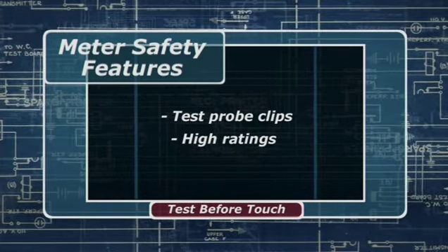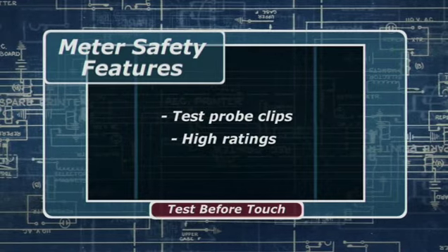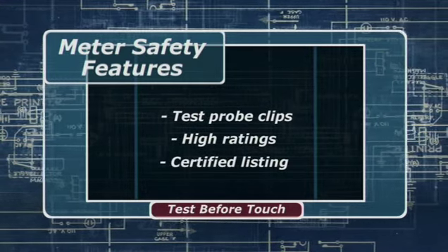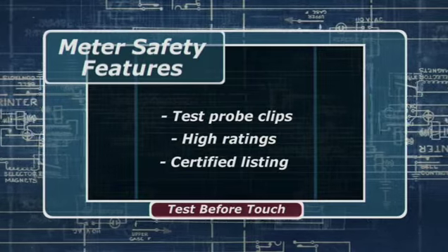And like we just talked about, you want your meter to have higher safety category ratings and a listing by a nationally recognized testing laboratory, like UL, to ensure that your meter meets minimum safety standards. And choose a quality meter from one of the well-known manufacturers. And don't go for the bargain price meters. Most of them aren't as well made, they don't have all the features you need, and they may be dangerous in an industrial environment. Your safety depends on using the proper test equipment. And don't assume that your meter's working correctly. Inspect your meters before each use. If you're working with a defective piece of equipment, you're working without protection.